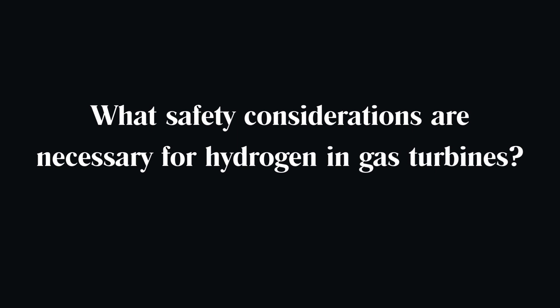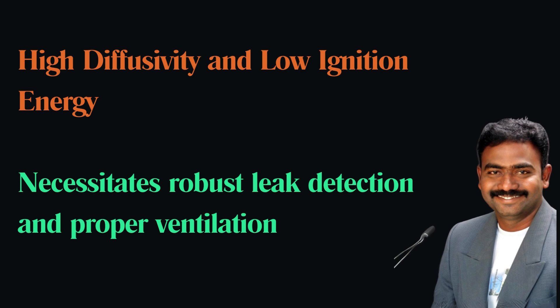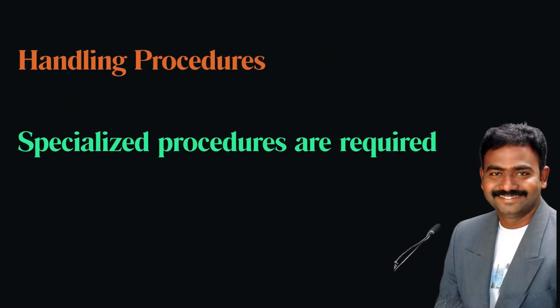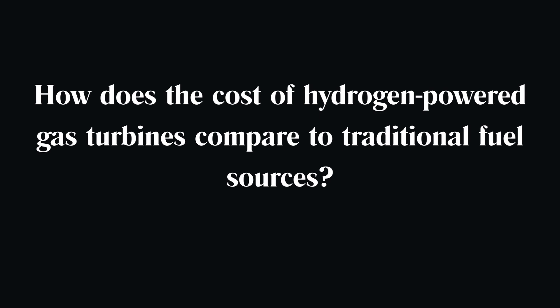What safety considerations are necessary for hydrogen in gas turbines? Safety considerations include managing hydrogen's high diffusivity and low ignition energy, which require robust leak detection systems, proper ventilation, and specialized handling procedures.